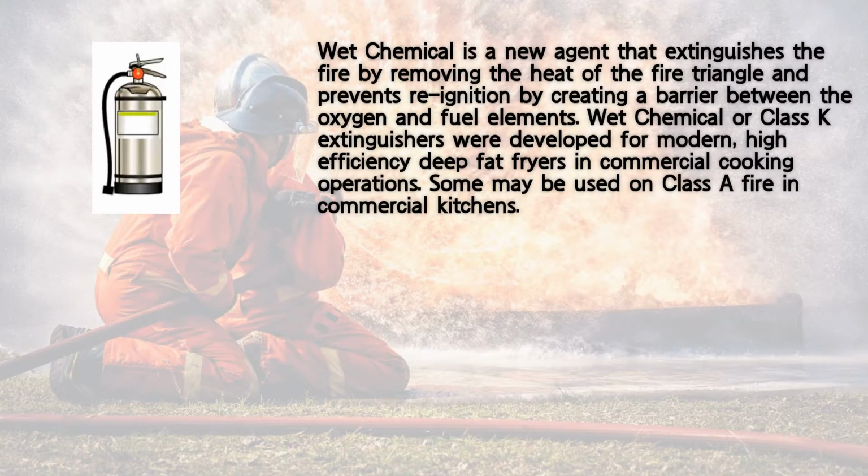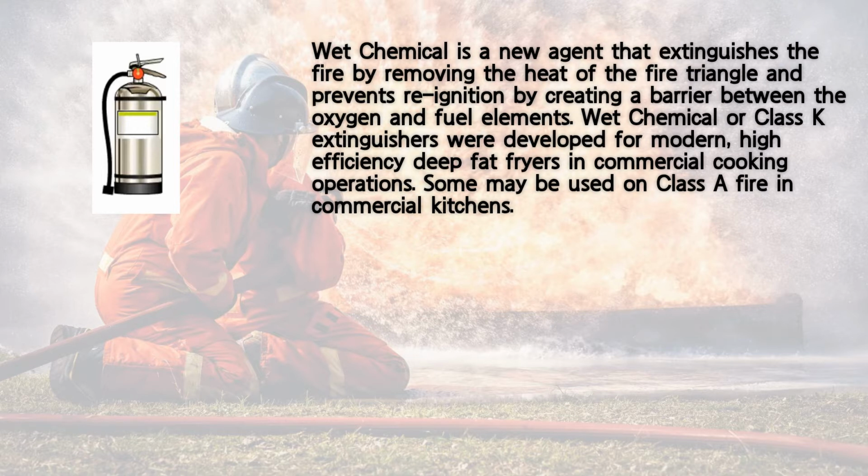Wet chemical is a new agent that extinguishes the fire by removing the heat of the fire triangle and prevents reignition, by creating a barrier between the oxygen and fuel elements. Wet chemical or Class K extinguishers were developed for modern, high-efficiency deep-fat fryers in commercial cooking operations. Some may be used on Class A fire in commercial kitchens.